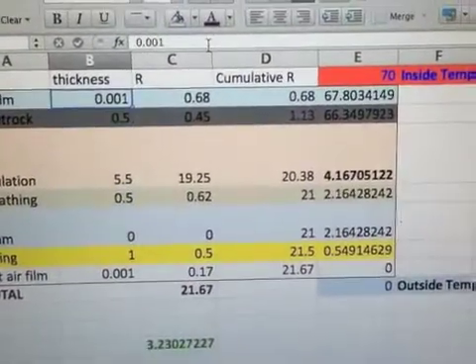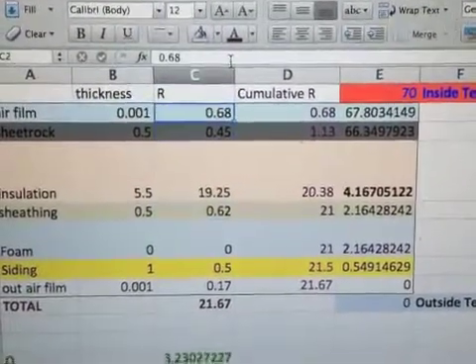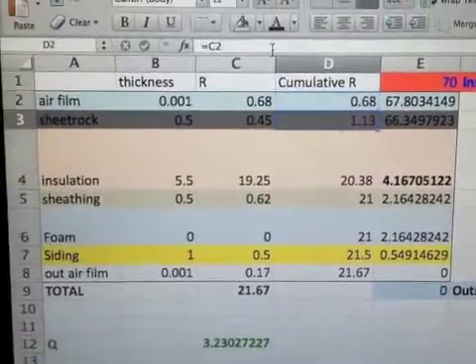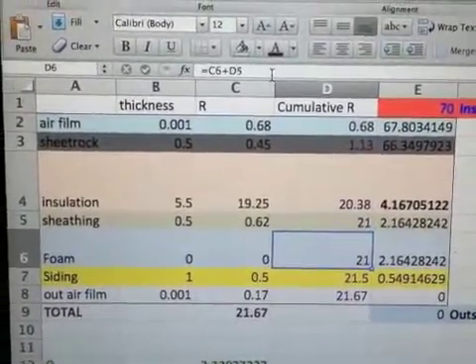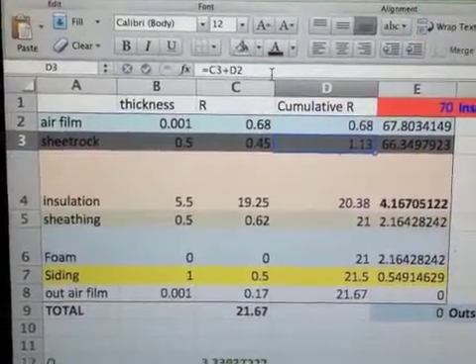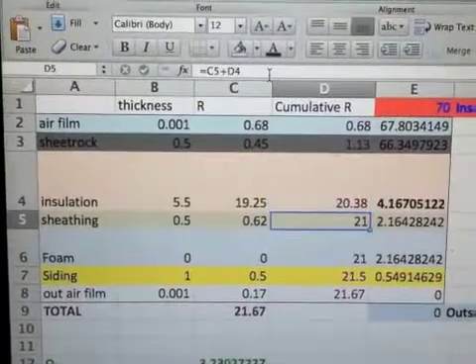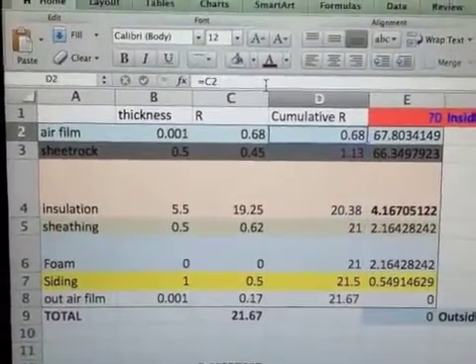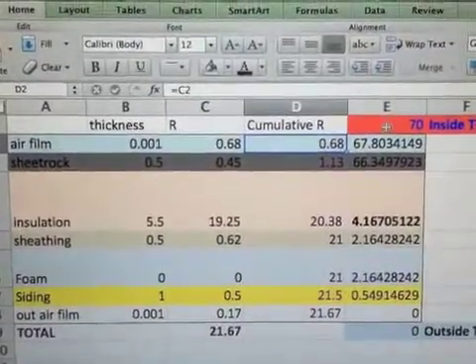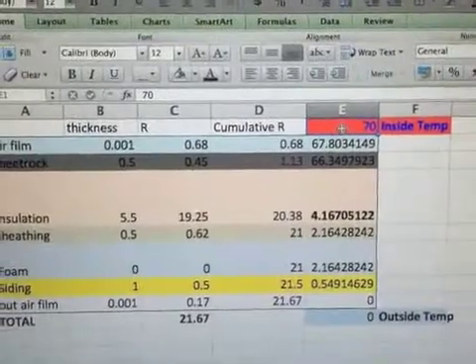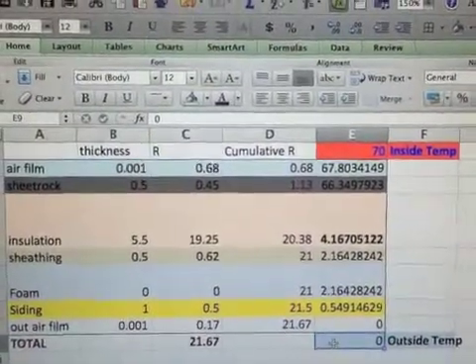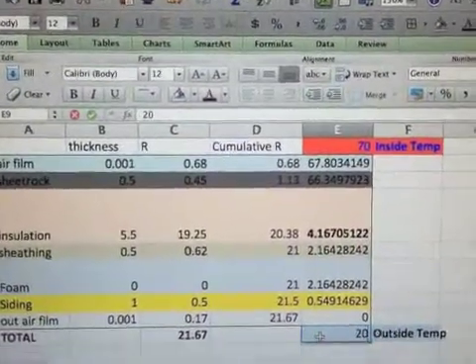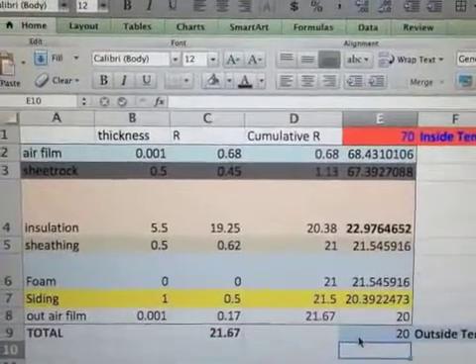Now we also have, so then we have the R value, either given or calculated, and then we have the cumulative R. So this is the exact same table that we set up by hand, but now we're setting it up in the spreadsheet, and it's calculating the cumulative R value for us simply by adding the cell directly above each one as we go from inside to outside, inside air film all the way to the outside. Now here we can set the inside temperature, which, as usual, we've set at 70 degrees, and we have to set an outside temperature, which I've set to 0 degrees, but we can set that, say, to 20 degrees, and it will recalculate things.